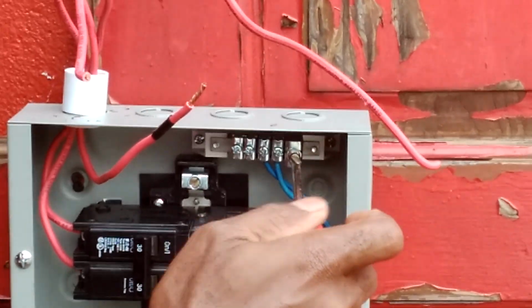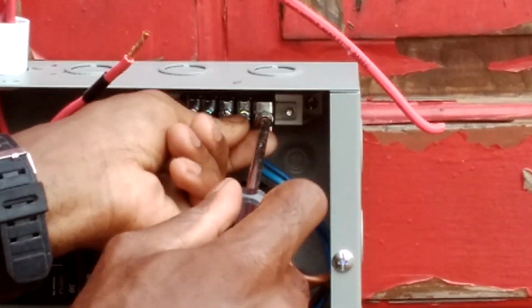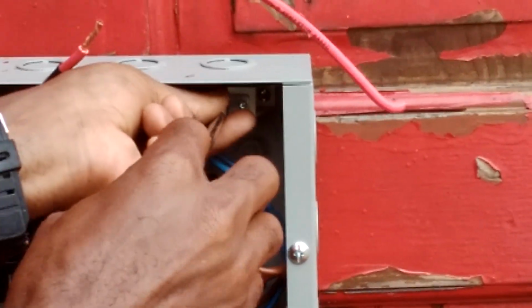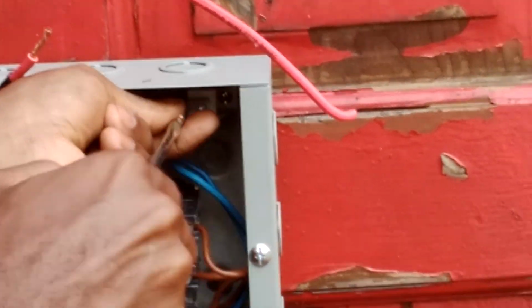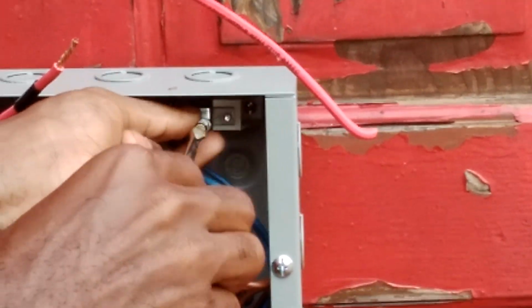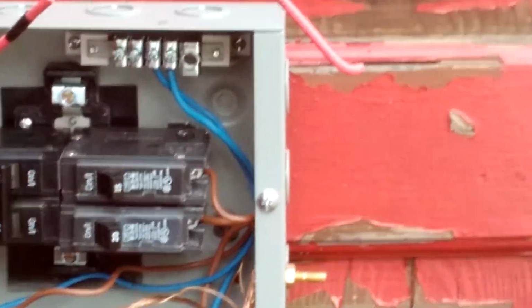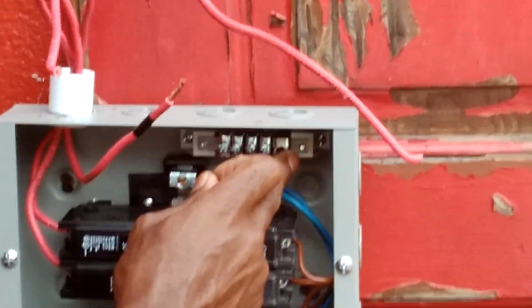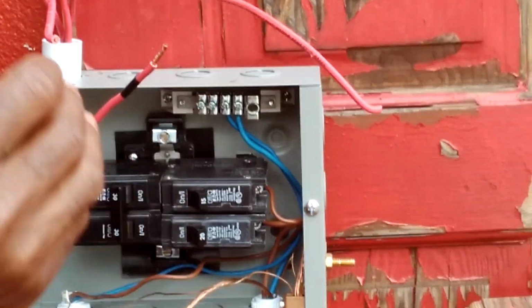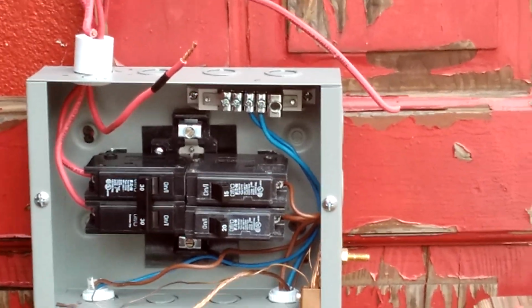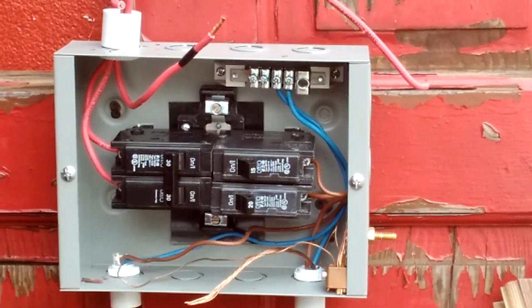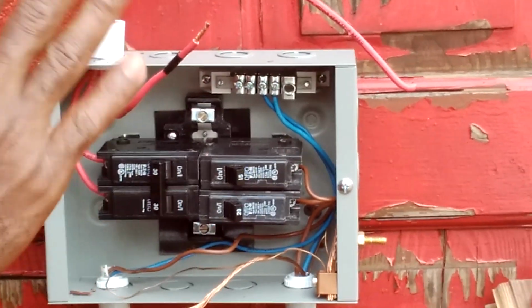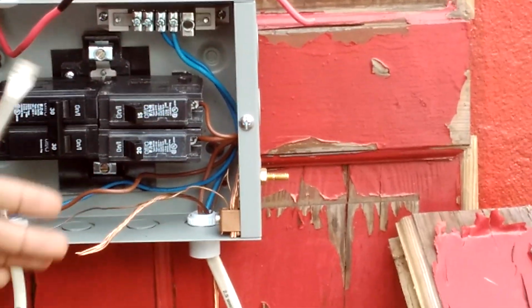I'm going to bring this screw directly out, because there's going to be more than one wire coming into this, and sometimes when the screw stays in there it can actually pose a difficulty fitting wires in. So you want to take the screw completely out when dealing with the main neutral, and I'll show you why. So you take it right out, and now we move on to the main neutral wire.